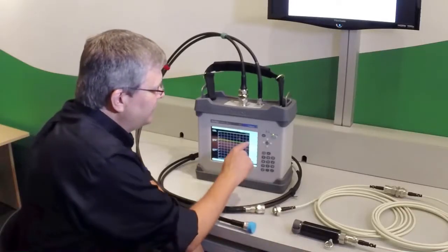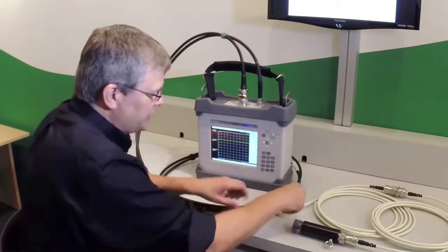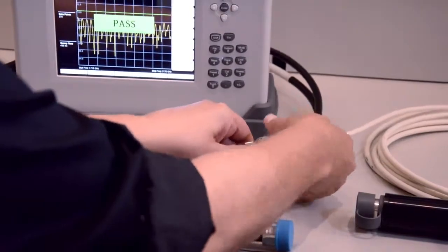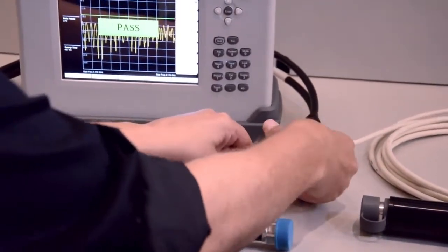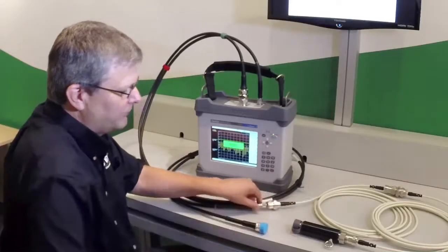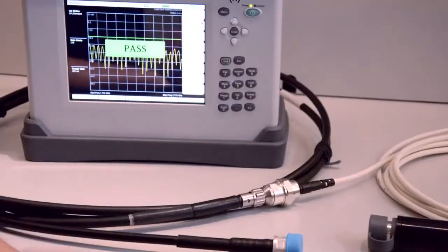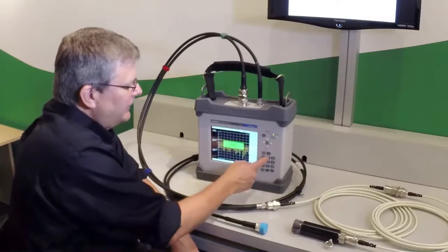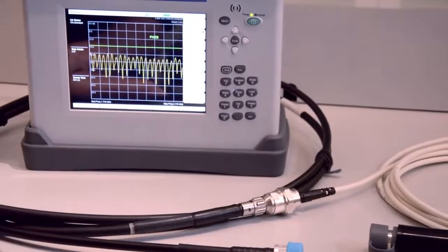The first thing we're going to do is do a quick return loss check of the system to see if this is a working system. Standard procedure says that you should always perform your sweep tests first before performing PIM tests. And so looking at this, I have a limit line set at minus 18 dB and we are passing, so we have a good system to start with.